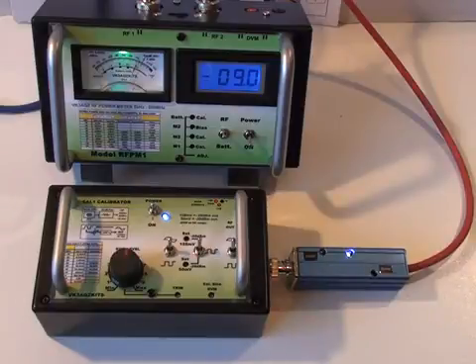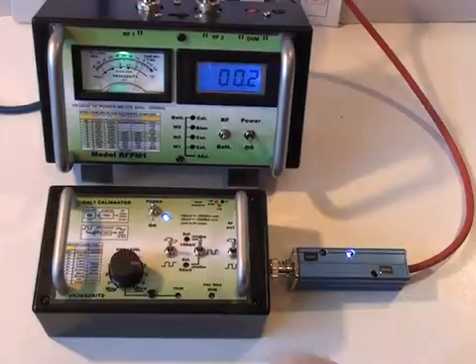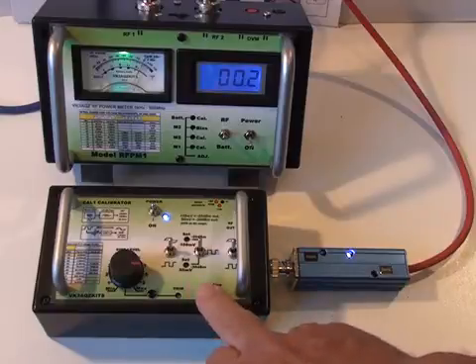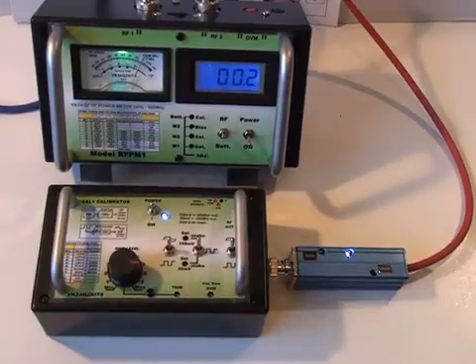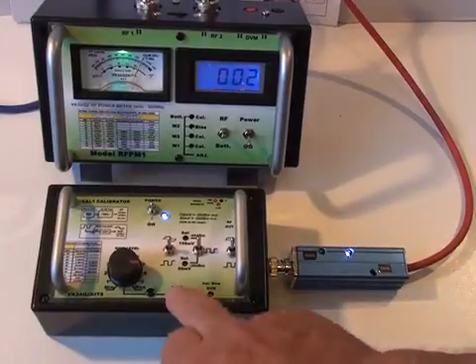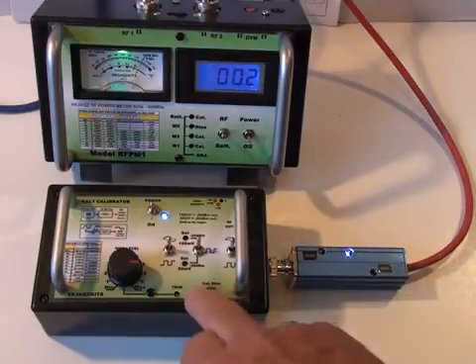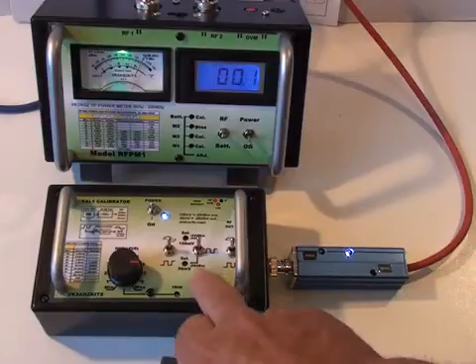In this particular calibrator, the sine wave is derived from a square wave. The low-pass filter offers around about a 45 dB attenuation at the second harmonic of the oscillator. The oscillator is running at 5 MHz, so at 10 MHz the harmonics coming out of the filter are quite low.